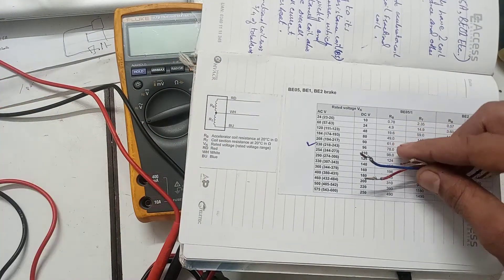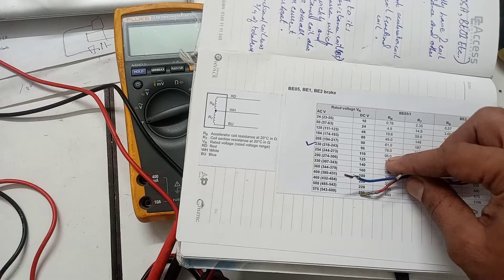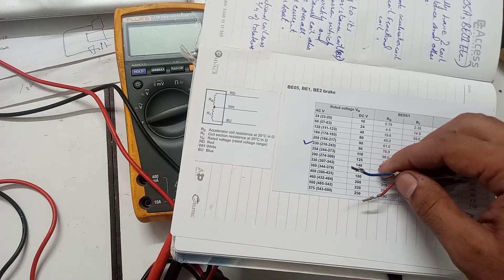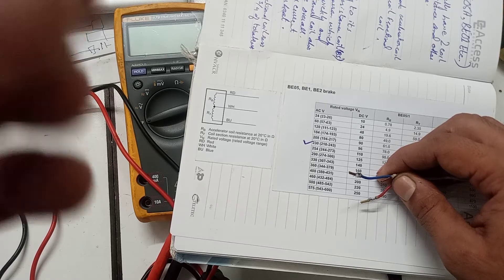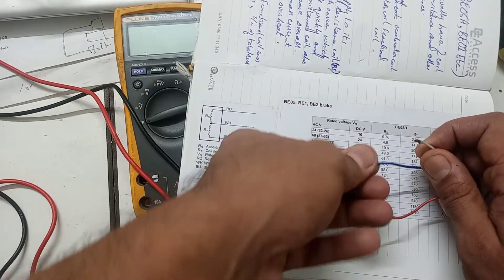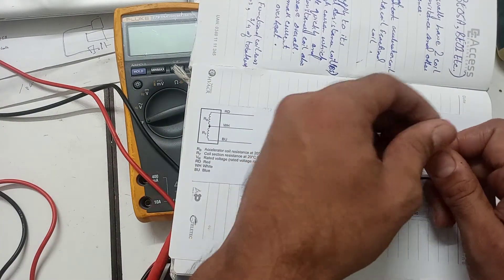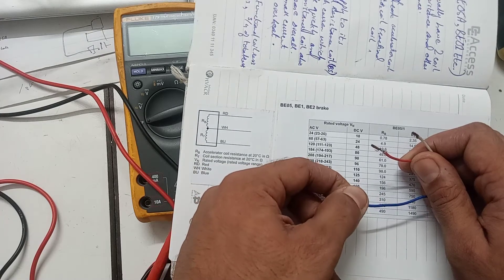Whenever we supply voltage to the rectifier and it provides output to the brake, within the first 120 to 150 milliseconds it only supplies to the accelerating coil, which has lower resistance, so the magnetic strength and current are both high. After 120 to 150 milliseconds, the sectional coil gets supply, so the overall resistance increases, the magnet strength decreases, and current is reduced — which prevents the brake from overheating. White and red are the accelerating coil; white and blue is the sectional coil.